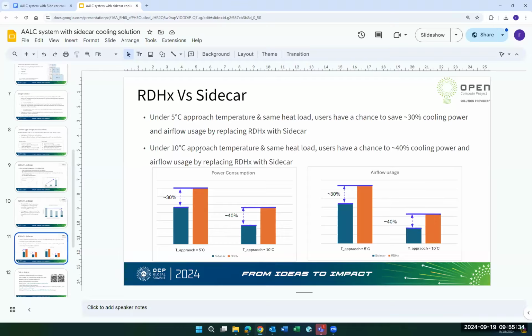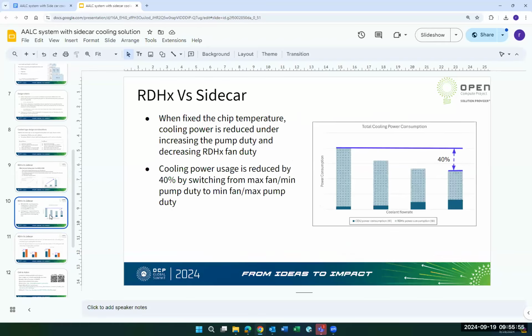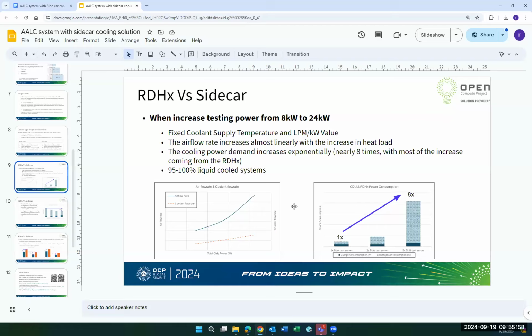Like flow rate will also help a little bit, but airflow is the major factor that's going to impact the approach temperature. So in this one it is a little bit more clear for me, but for the top two slides, it's not that clear, and it would be nice to have one sentence on the reason.